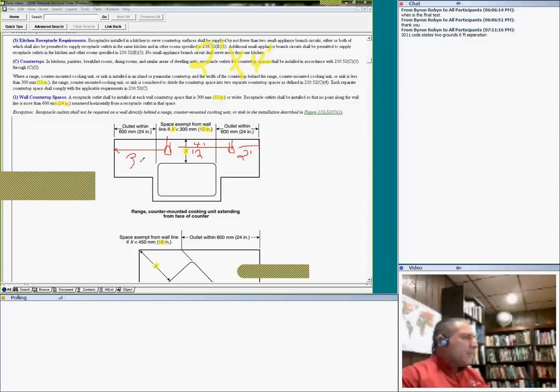Suppose this is 3 feet, right? Then I need another receptacle here, because I have to maintain no more than 2 feet from this side. Okay? So then does it count? About this 2 by 4, I always remember it as 2 by 4 on the countertop. Every 1 foot or more, you need a receptacle at least. That's the top. And please remember the 18 and the 12 are again for your journeyman exam.